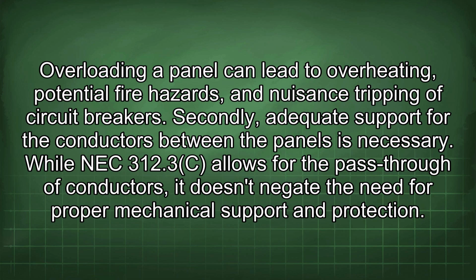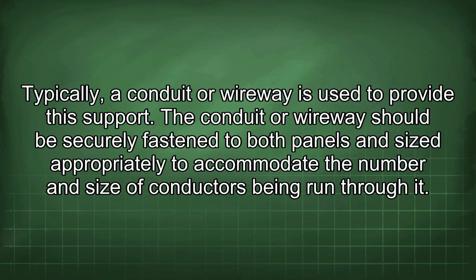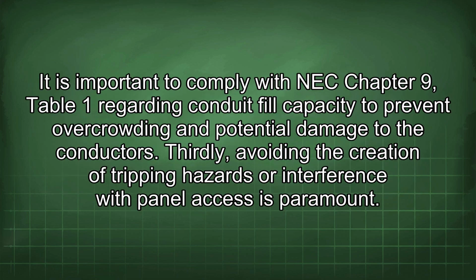Secondly, adequate support for the conductors between the panels is necessary. While NEC 312.3(C) allows for the pass-through of conductors, it doesn't negate the need for proper mechanical support and protection. Typically, a conduit or wireway is used to provide this support. The conduit or wireway should be securely fastened to both panels and sized appropriately to accommodate the number and size of conductors being run through it.